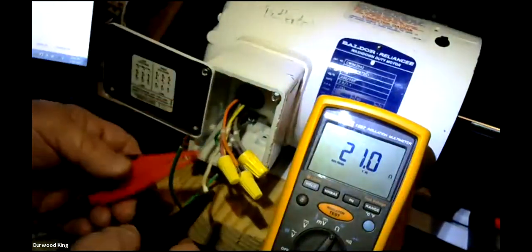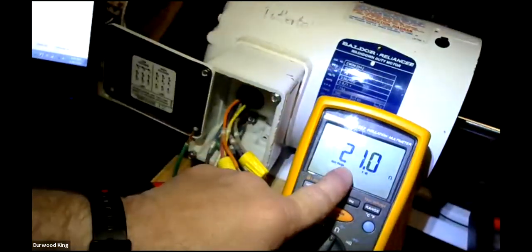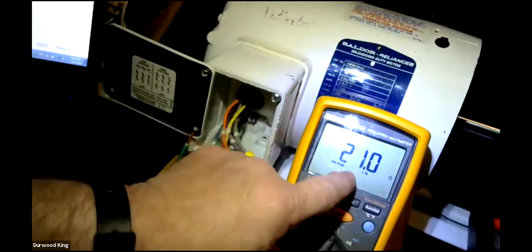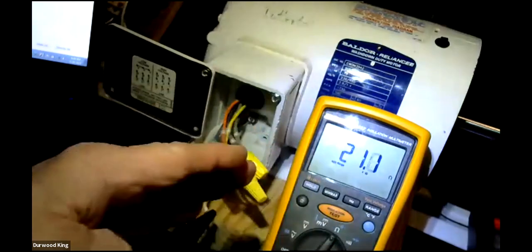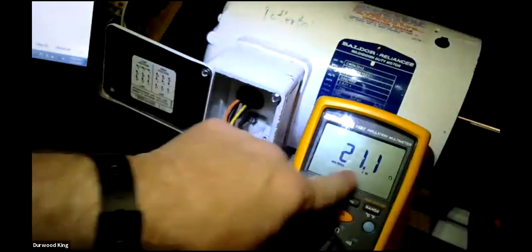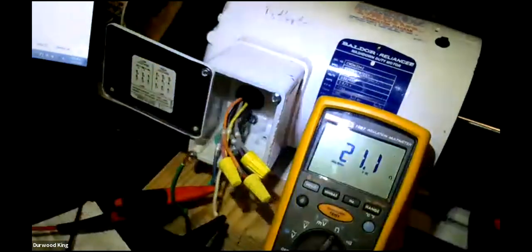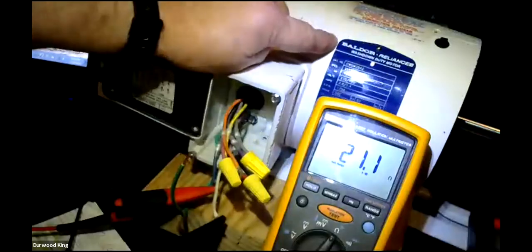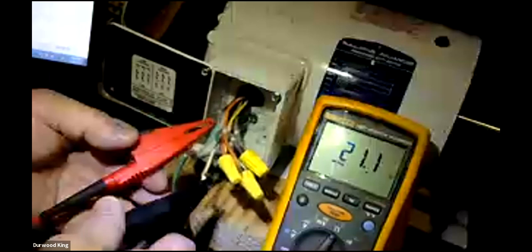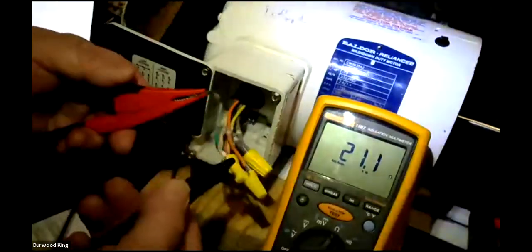But the rule of thumb is this: the larger the motor, the less that's going to be. Really larger motors, if you get around 10 horse and up, that number is going to be way down close to 0. It may even be less than 1 ohm. And the smaller the motor, the smaller the wire, and the higher the resistance, because the windings inside the motor are really small, and so they have more resistance when they're real tiny fine wire. It all boils down to the size, the gauge of the wire inside the motor. The lower the horsepower, the higher the resistance. Yes, sir. Absolutely.